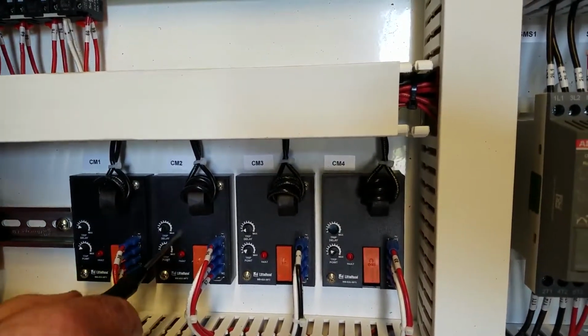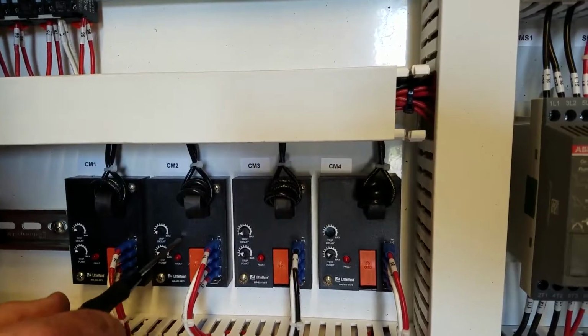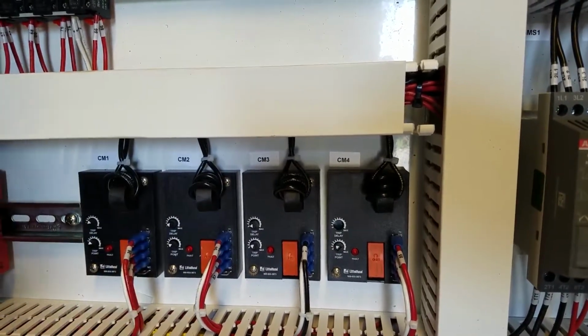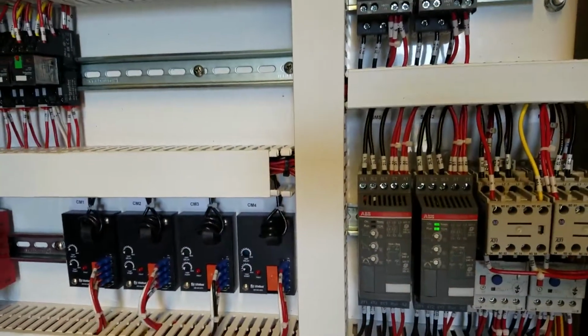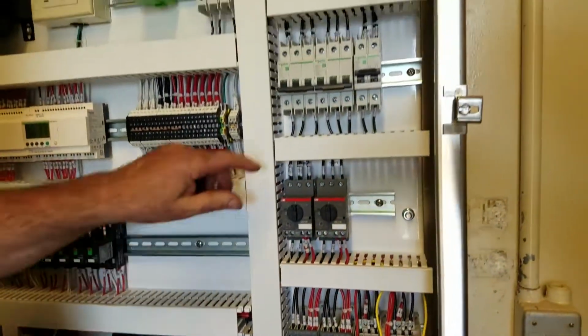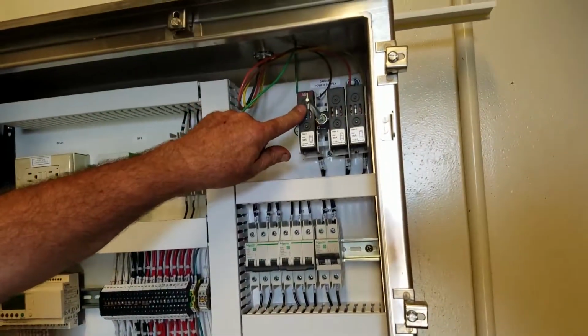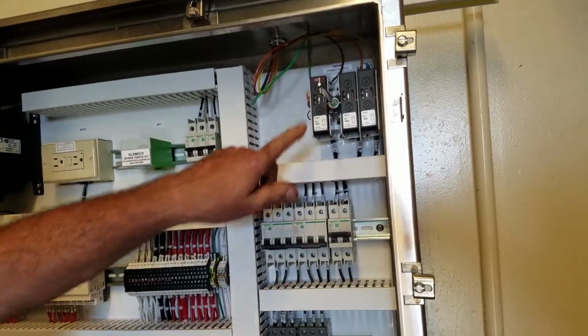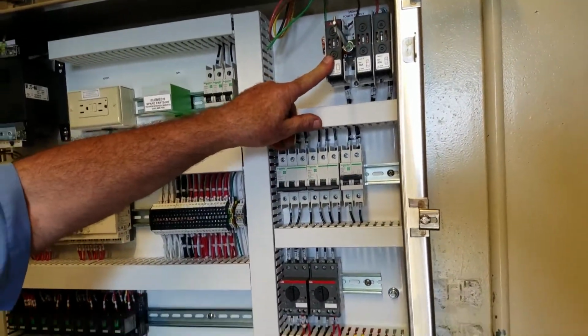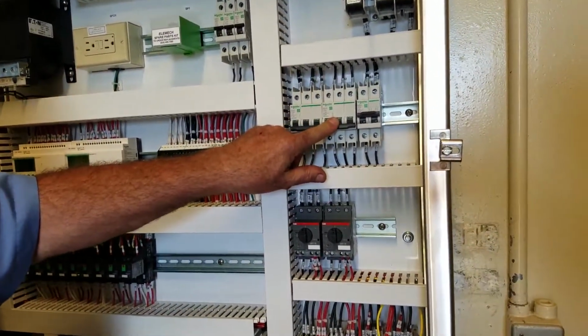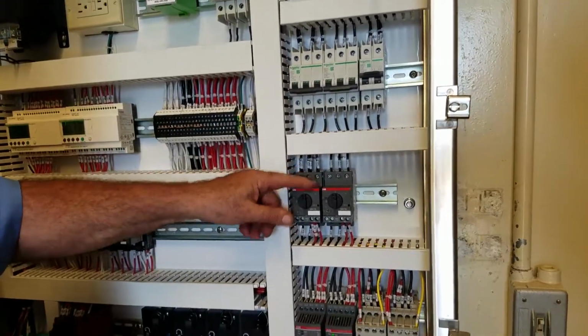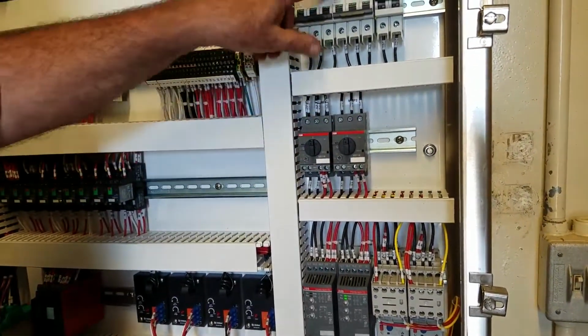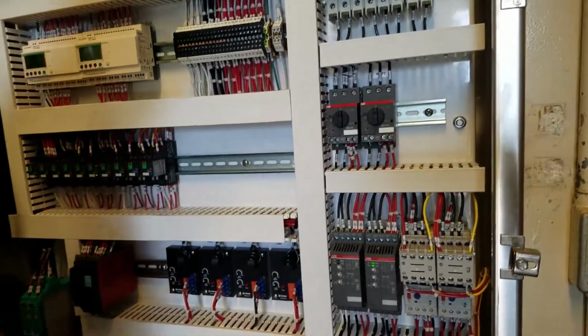This is your primary load protection device. The secondary is built into the soft start. Your tertiary protection is here, and the level 4 protection are these fuses. You blow a fuse, you got a big problem. You trip a circuit breaker, you got a big problem. Circuit breakers for the screens are here. These are for the press and the conveyor.